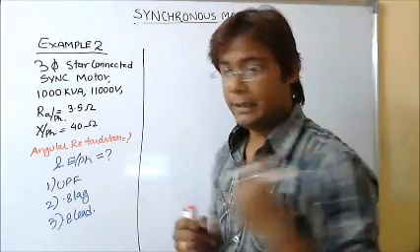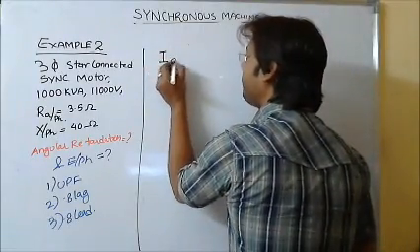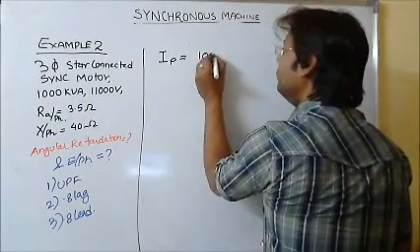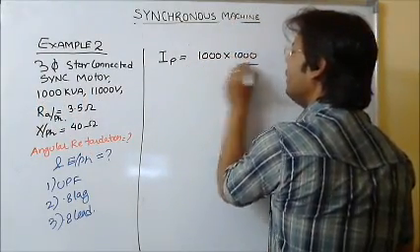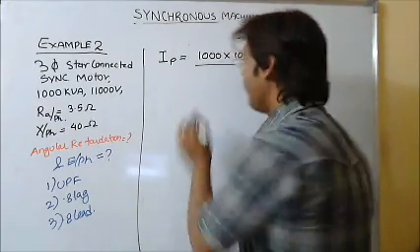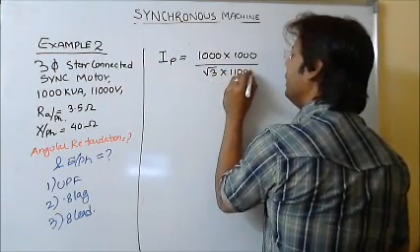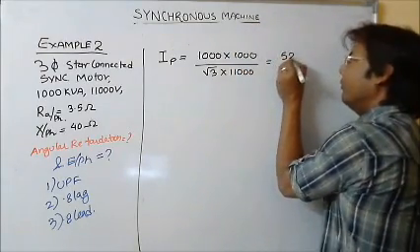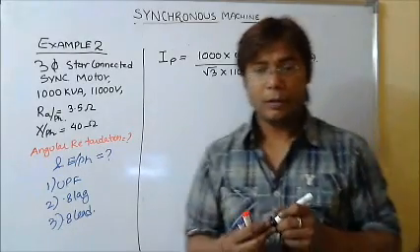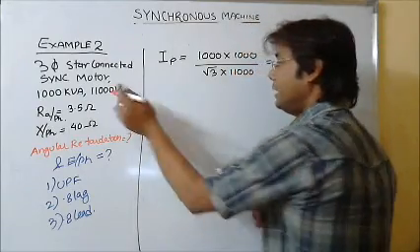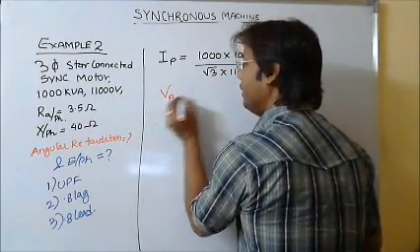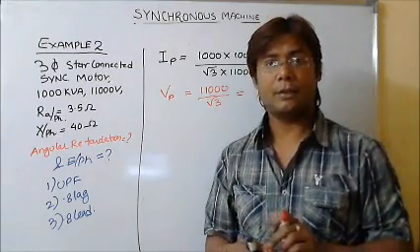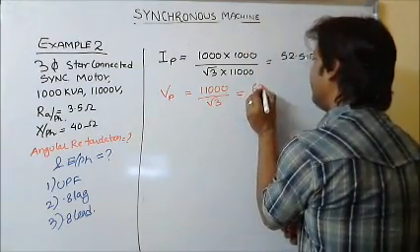First of all, I have to find the full-load current I_P, which I can get from: I_P = 1000 kVA divided by root-3 into 11,000, giving I_P as 52.5 amperes. Then the phase voltage V_P equals 11,000 divided by root-3, which equals 6351 volts.